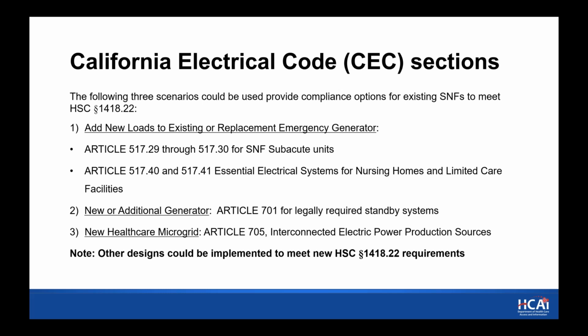California Electric Code section. This is what we talked about, and I'll go into these a little bit more. I'm presenting 3 scenarios that could be implemented to provide compliance. Obviously, there are more scenarios that could be pursued, but I've identified these 3 to demonstrate how we would apply code to these options. First is simply using the existing facilities, the existing emergency generator, or replacing the existing emergency generator and using your existing emergency system if capacity allows. The second would be a separate generator, independent from the emergency generator, that only backs up the AB 2511 loads. And the third is a new healthcare microgrid, which would back up the entire site. So we're going to go through those now.